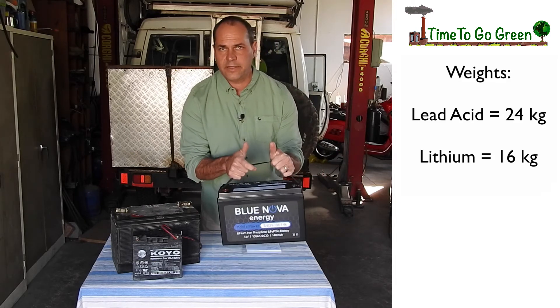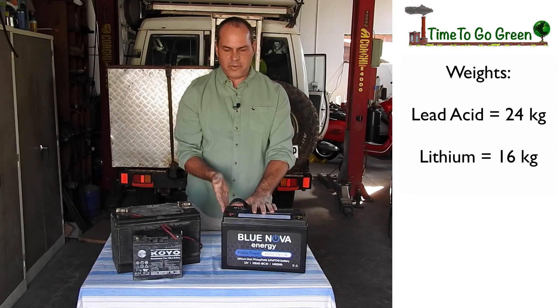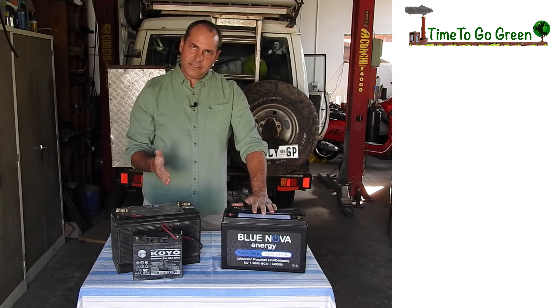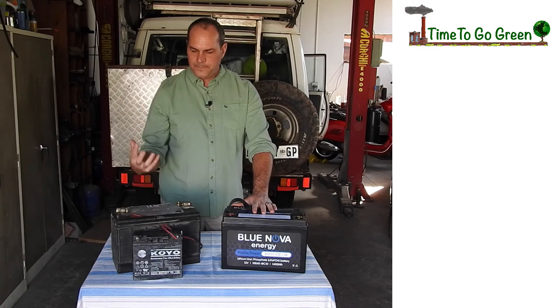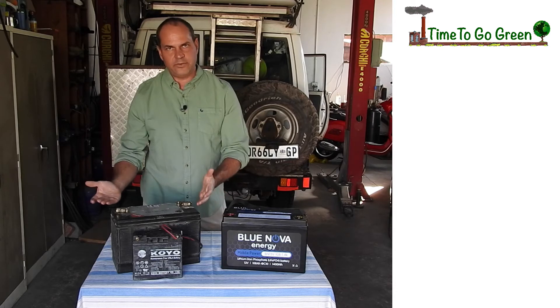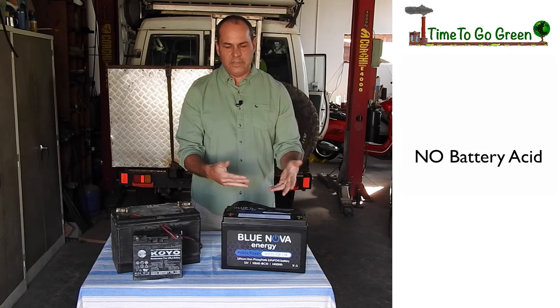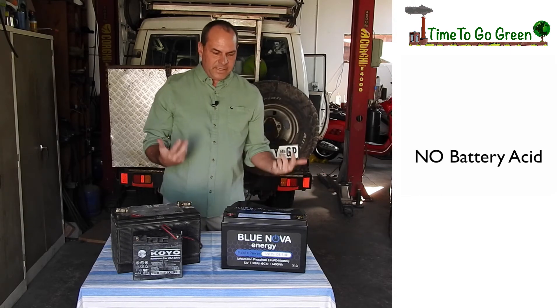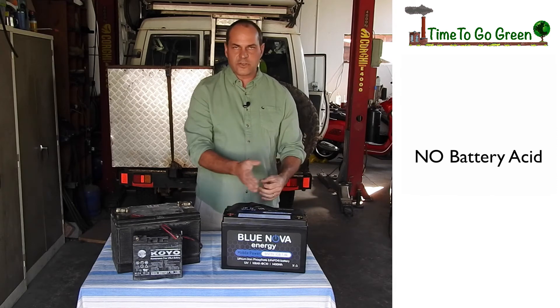The second point is weight — lithium batteries are very light compared to lead acid; I'm not even going to bother to pick up the lead acid. The lead acid case contains lead plates submerged in liquid or gel — it's essentially a flooded battery. The lithium battery comprises a bunch of small cells, like double-A batteries, packed in very tightly, soldered together with a battery management system on top and encased in a black case. There is no acid inside — it's just a series of small batteries, all lithium iron phosphate, packed together to make one big battery.